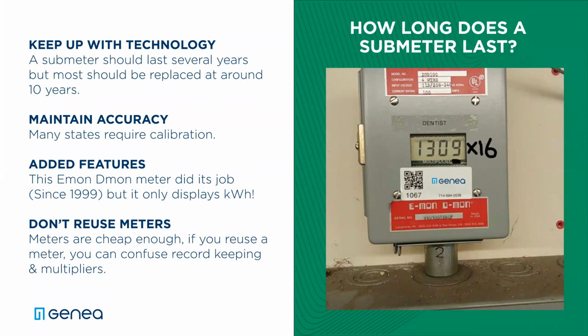And the last thing we hear all the time is, I had this meter in my stock room, I'm going to reuse it over here for this tenant. It sounds good, but meters are so cheap these days - why risk it? We've seen too many times where somebody has a meter that had one set of CTs on it, and when they move it to the new place, they put two sets of CTs on it. So they change the multiplier, as you see in this picture here. Then it gets moved somewhere else, or somebody can't remember why they did something, and all of a sudden we're not sure whether it's reading right or not. Is it the right multiplier? Does it have the right number of CTs on it?